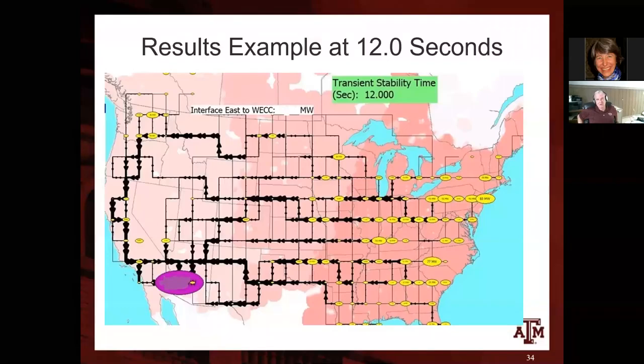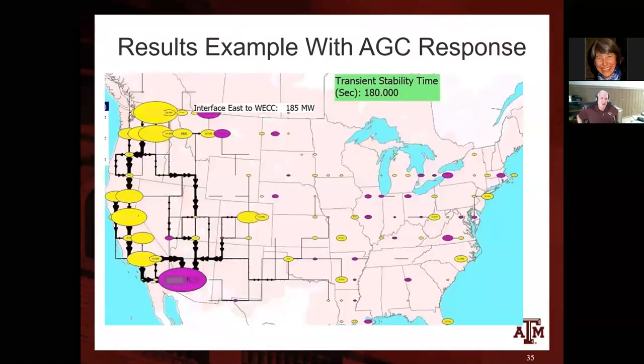Those black arrows show the change in power flows across the system, going across our interface. That's why you see the interface loading going up, because we get this automatic response from the generators in the East. Then when I run it at 180 seconds, the frequency has mostly come back to where it should, close to 60 hertz. Now the yellow ovals are showing where the makeup power is occurring after the automatic generation response.